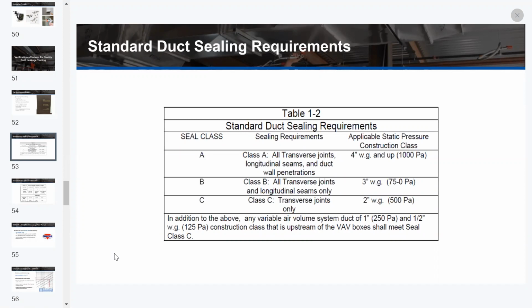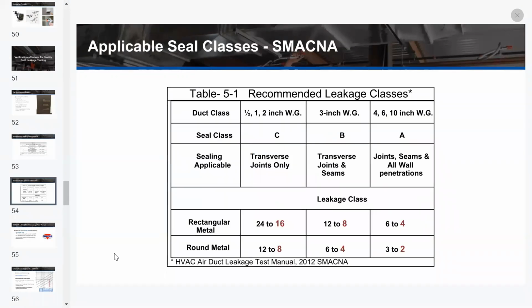With the focus on indoor air quality and SMACNA's role in this, they're tightening those specifications. On the next slide, you can actually see this. It's showing the applicable seal classes for rectangular and round metal ducts, and you can note the changes. For example, under transverse joints only for rectangular metal, it's changed from 24 to 16. The 24 means you're allowed to leak 24 CFM of air for every 100 square feet of duct surface area, and that's been brought down to 16. You can see SMACNA is starting to tighten up their requirements as well.